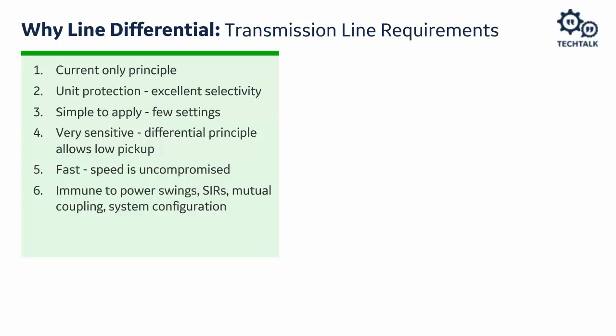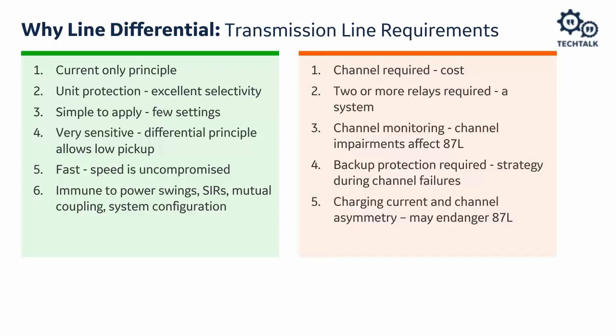However, there are some disadvantages. We need a communication channel — an additional cost. We need two or more relays; it's a system that cannot work on its own. We need channel monitoring because channel impairments will affect 87L. We need backup protection when the channel fails. And there are unique challenges that only exist for 87L: channel asymmetry and charging current.